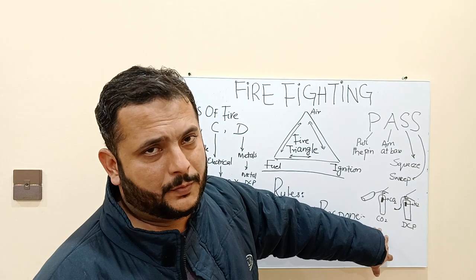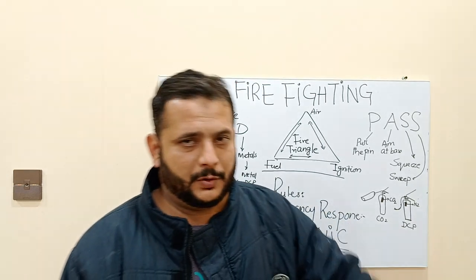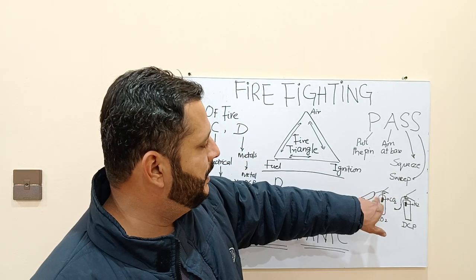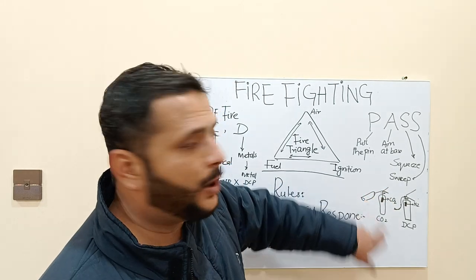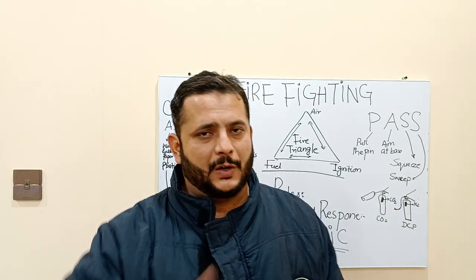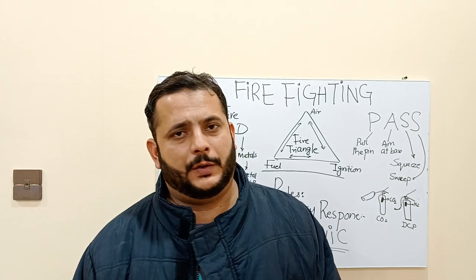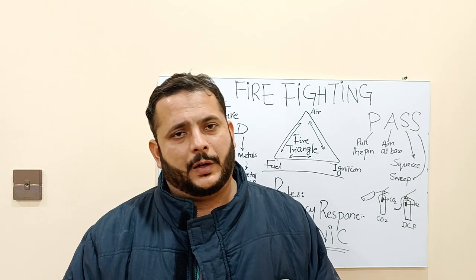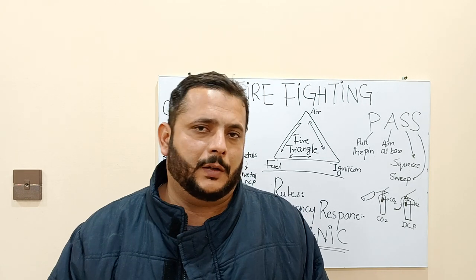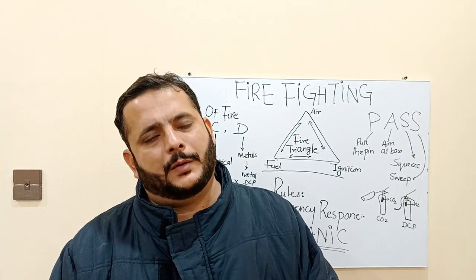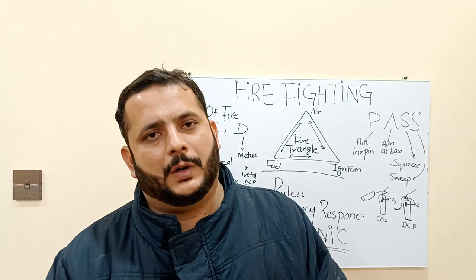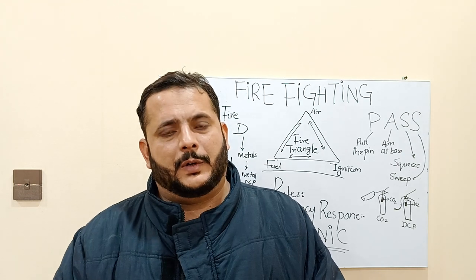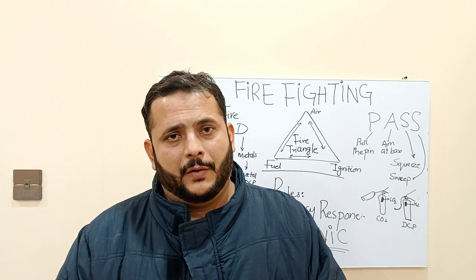The second type is the CO2 fire extinguisher. These two types are majorly used in organizations. The CO2 extinguisher has a CO2 cartridge inside, a pin, a trigger, and a horn-shaped hose. When you see a horn-shaped hose, it means it is a CO2 fire extinguisher. Also, there is no gauge on the CO2 fire extinguisher, because CO2 is a gas and in a closed container it always has some pressure. Even if there is a small leak it can still work for some time when required.